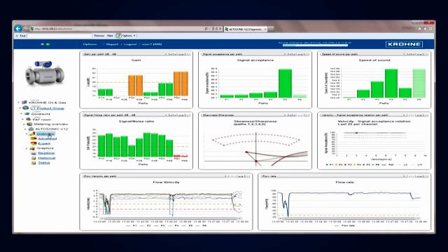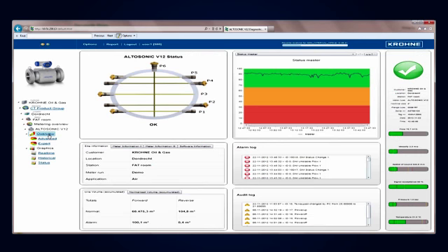If we go to the overview screen, you see nothing yet. It takes a little bit of time to take the averages. So in a minute you're going to see that the flow profile has been distorted and the meter will go into warning mode. And you just saw the meter did not even go into warning. The flow profile distortion is so bad, as what you saw that we caused.